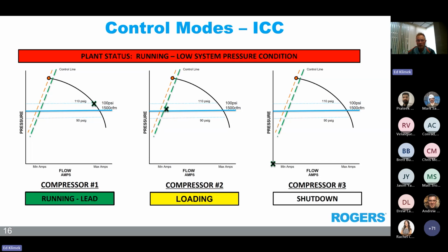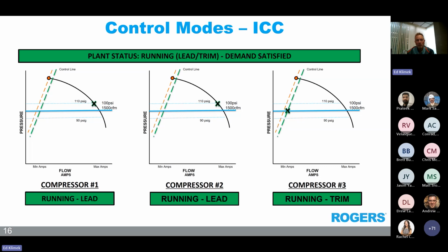With the system pressure still low, it starts up number 2 and loads to its minimum operating point. But noticing it was still low, it loaded to 110 psi. With the system still low, it started number 3. Demand was satisfied, but then it went low again, so it's loading number 3. Now that number 3 is able to meet the required system demand as the minimum load, now that all 3 compressors are running, you can see that as the demand increases, drawing down the system pressure, which results in the trim compressor, which is number 3.